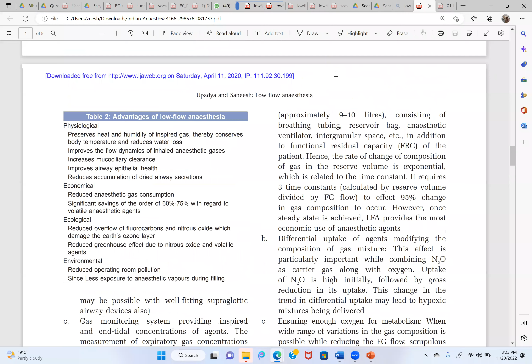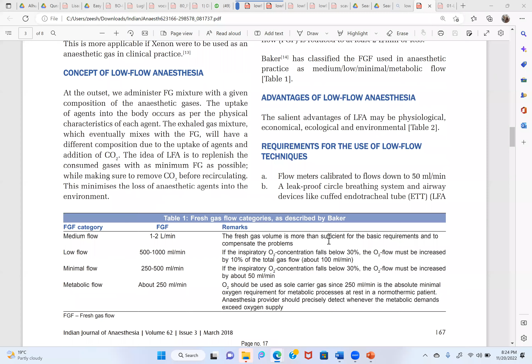Okay, a few things I just forgot to mention. One of them was when you are having any leak in the circuit. If it is more than 100 ml, so if you are giving only 500 ml and you happen to lose around 200 ml of volume, it will have a big impact. Similarly, if you are using side stream end-tidal CO2, it itself will be a problem, because side stream will take a lot of volume. So there should be a mechanism that the volume which is taken should come back. Otherwise, it will create a problem. Similarly, if you have a leak in the circuit, even with an uncuffed endotracheal tube or supraglottic airway devices, if it is not properly sealed, then you will lose this benefit.